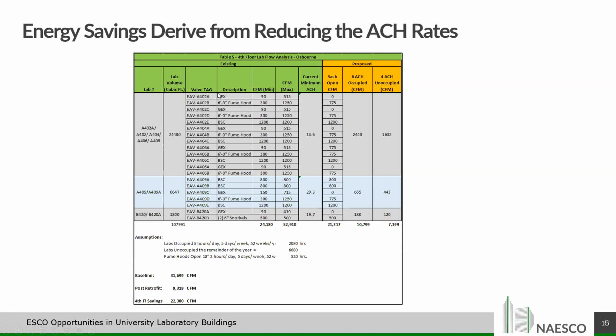What you do is identify each piece of exhaust equipment in the lab, whether it's general exhaust, fume hoods, biosafety cabinets, or snorkels, and what their exhaust rate is. Now, this analysis was done for an existing VAV lab that was over 10 years old, so it was still ripe for a retrofit. You can see they had a minimum valve exhaust and a maximum valve exhaust. So there are already valves there, but they had a minimum and a maximum. In just calculating the air change rate at the minimums, we were still at about 13.6 air changes per hour in this lab, almost 30 air changes per hour in this lab, which means every 2 minutes you're changing out the air in that lab with 100% outdoor air. And this one was at about 20 air changes per hour.